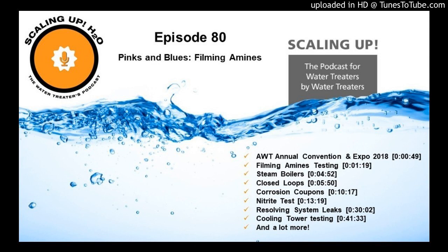Well, I told you about the lid and the closed loop filter. If you could see the picture, go to my show notes page and look at the presentation I put there. It's the same presentation that I gave at the Association of Water Technologies convention. You will see the most beautiful black magnetite you have ever seen in your life. And you folks out there as water treaters, I know you feel the same way. That is water treaters' nirvana.